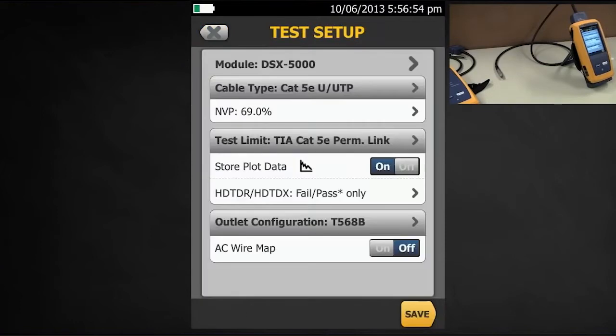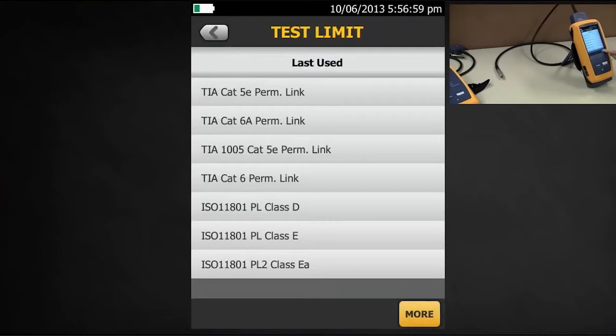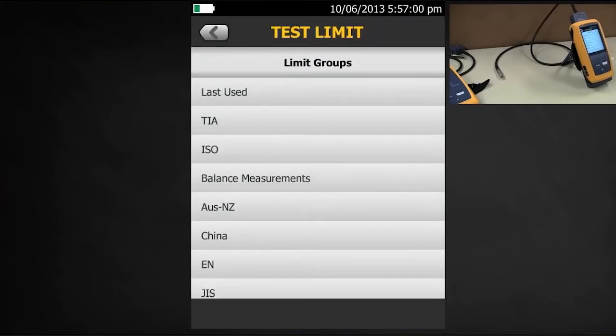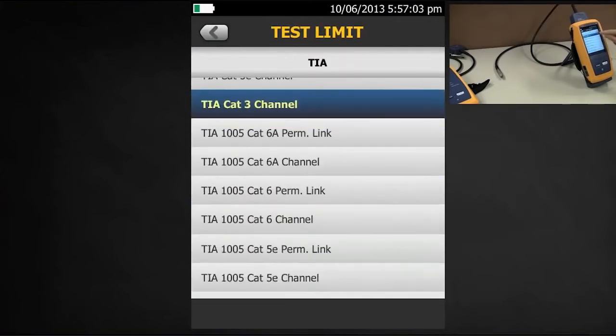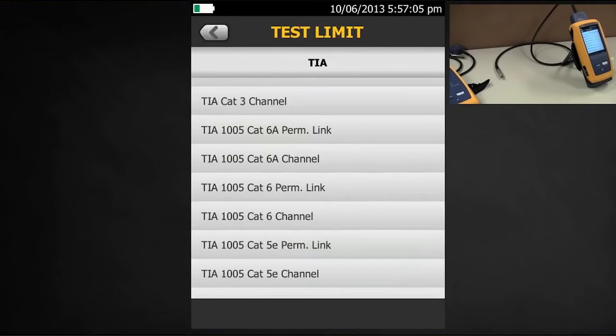So what we need to do here is change the test limit. Tap Test Limit, then More, then TIA. If I just go down the screen, I see all my CAT6A and CAT6 and CAT5e permanent link options, but now I also see one that says TIA 1005 — that's my industrial Ethernet standard that's going to allow me to do a two-pair test.